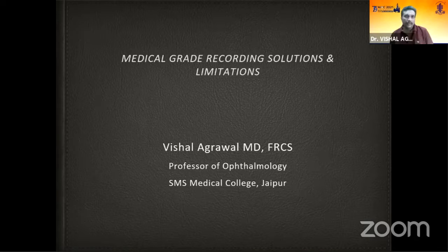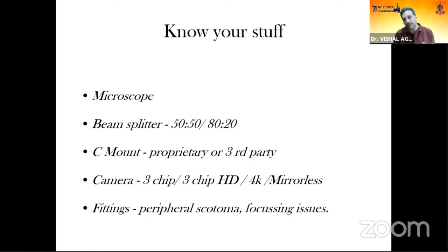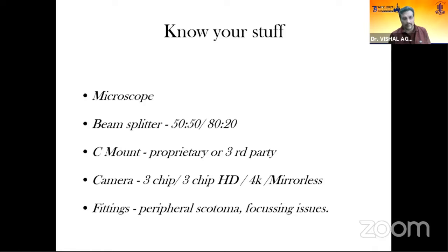I'll be speaking on medical grade recording solutions and their limitations. To start, for any recording system you should know your equipment — your microscope model, what beam splitter you have, and the C-mount, whether it's proprietary or third party. You should also know what type of camera equipment you have — 2D cameras like three-chip HD, 4K cameras, or mirrorless cameras — and all fittings should be tight and steady with no peripheral ring protruding out, which can lead to scotomas and focusing issues.